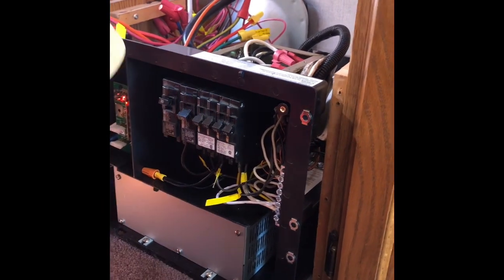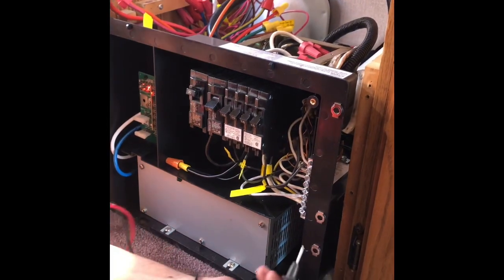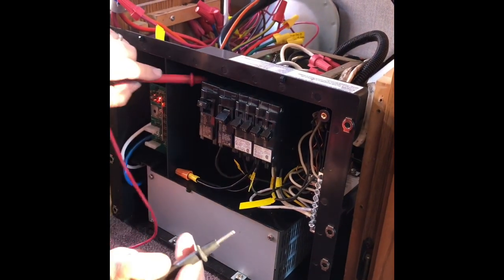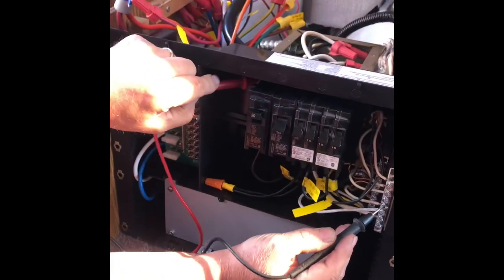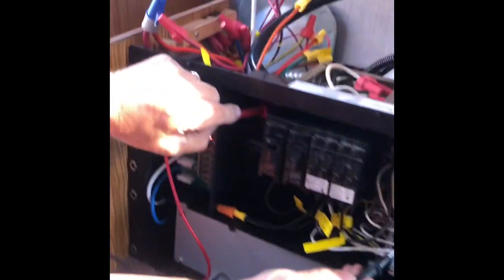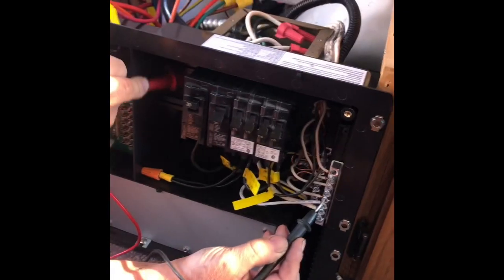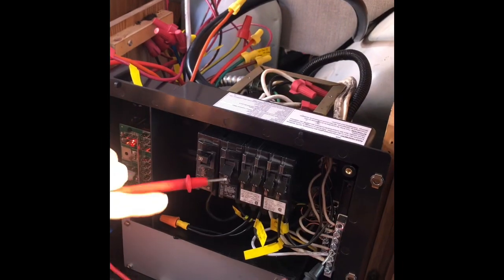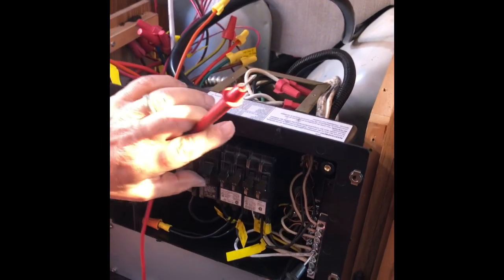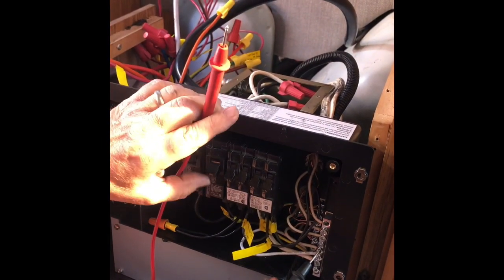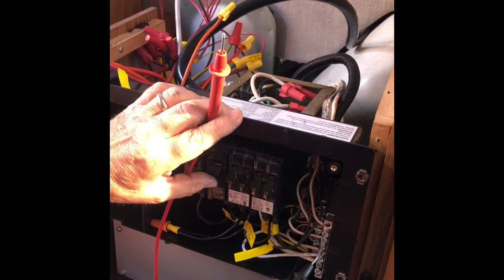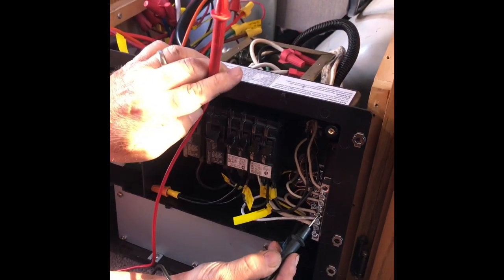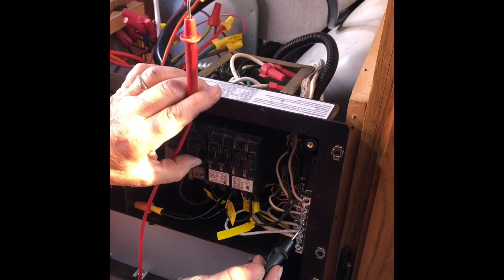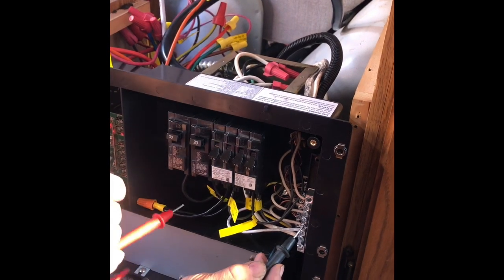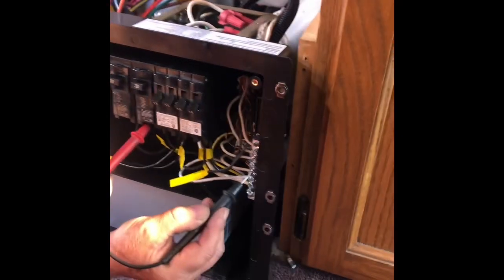Now watch. Okay. So now we should have power up here on the bus bar with that thing closed. I bet we do, and we do. Okay, so we got power up on the bus bar with that closed. So what was this 20 ampere again? That's the AC. I'll just close these and check for power. So that's the air conditioning outlet. You shouldn't get anything in there. Yep, now we got power there.